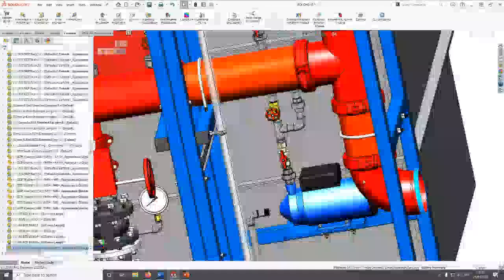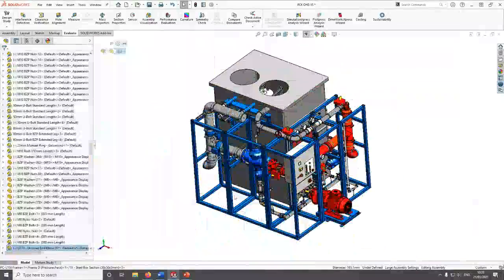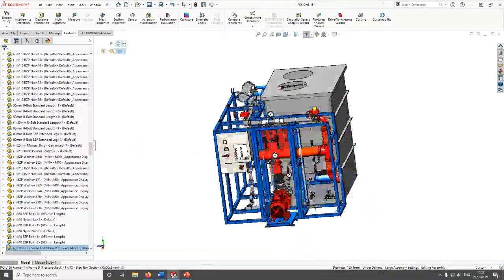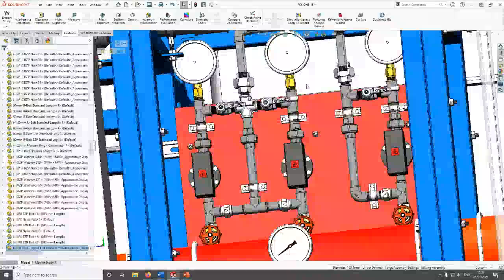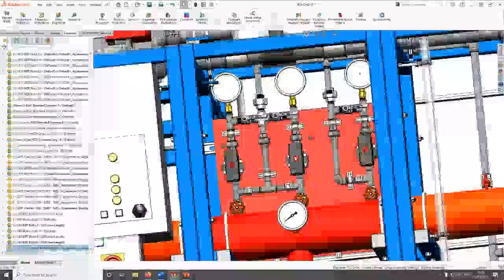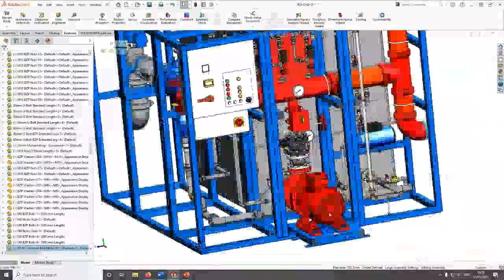Okay, so pressure check is good for running directly off the town main. That means it's like a hybrid solution. It is an enhancement to the town main, which means that where possible, it will just use the town main. Obviously, the fire pump is an approved fire pump, very reliable. But if the fire pump were to break or require some servicing, then we do still have the option of a direct town main supply and feed. However, when the pressure is not sufficient, so when we have a sprinkler head activation, that will obviously cause a drop in pressure. That drop in pressure is picked up by our pump initiation board, which is again very similar to what you would see in a normal pump house. So that drop in pressure would then call for the fire pump to start up.